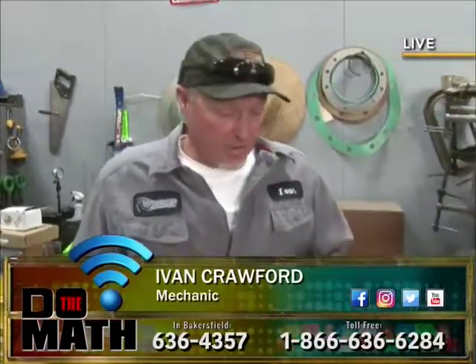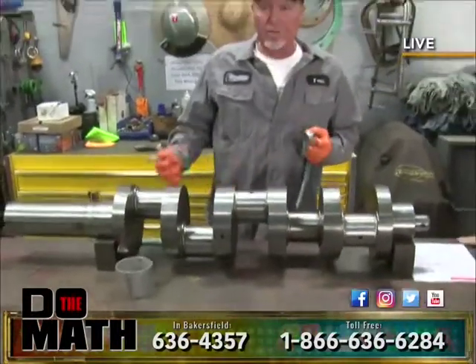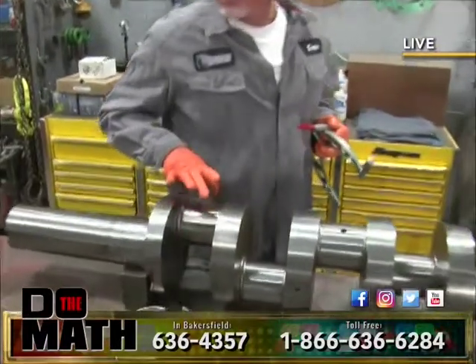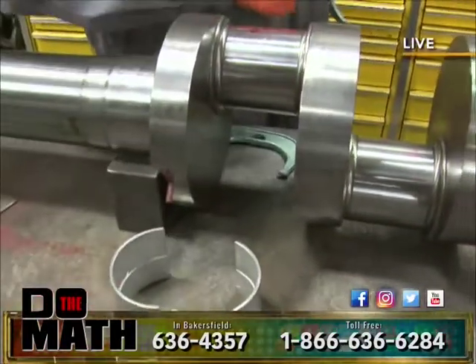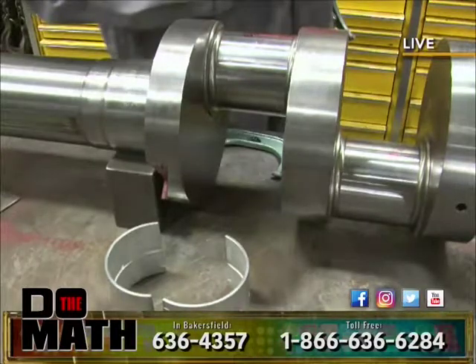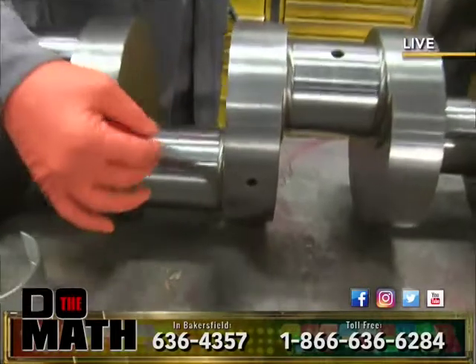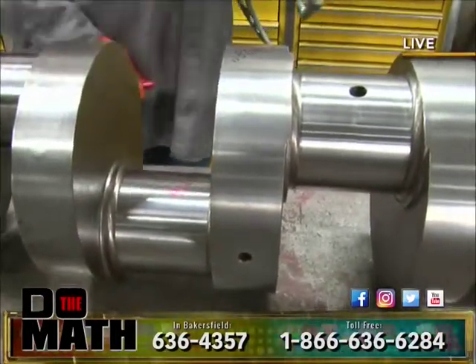So we use a mic to check clearances, which tells how much wear is between this bearing and this journal. So now this is a piece that's been repaired or refurbished. This would be a repaired piece. And what we do is we go and grind off these parts right here, and then they'll spray them back up or weld them, and then turn them back down to fit.